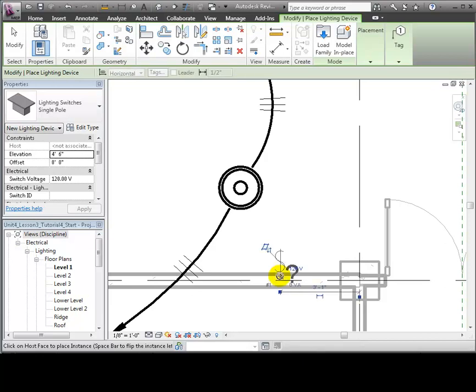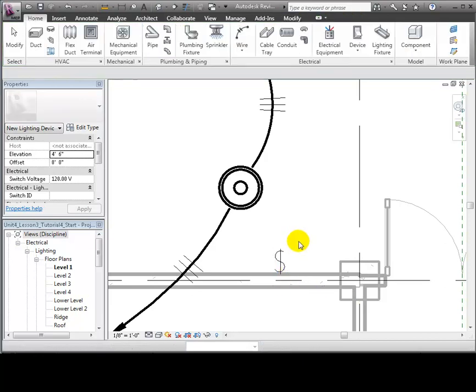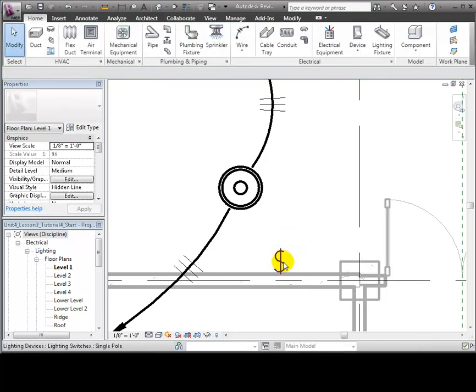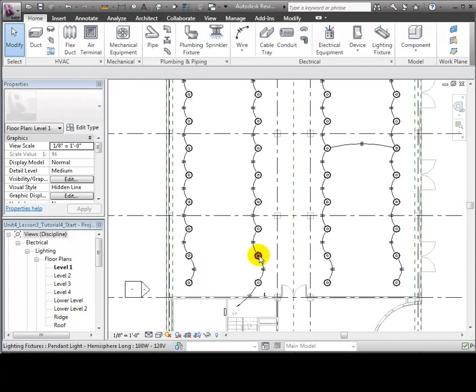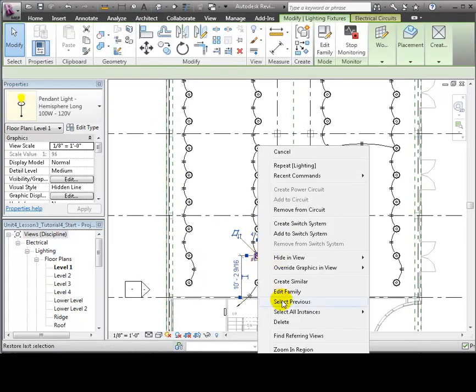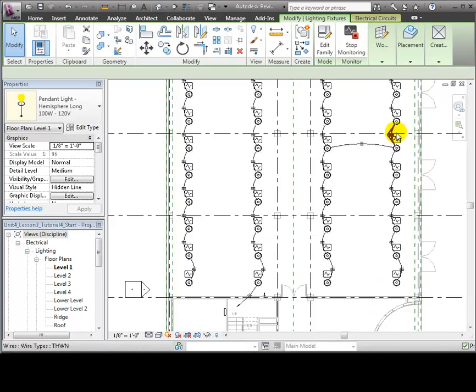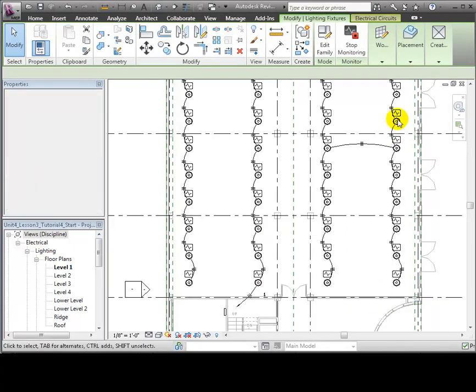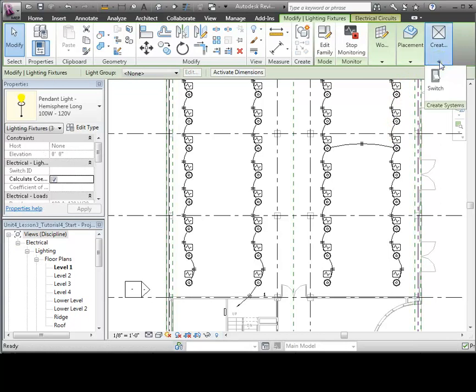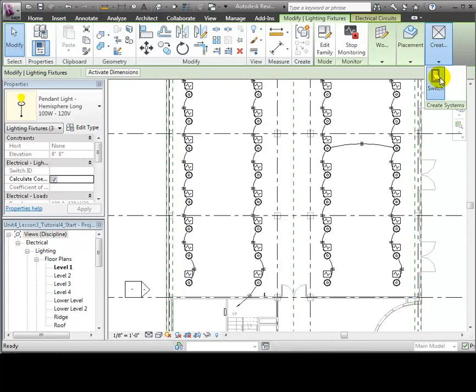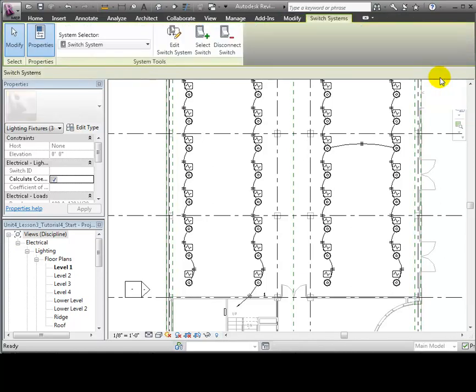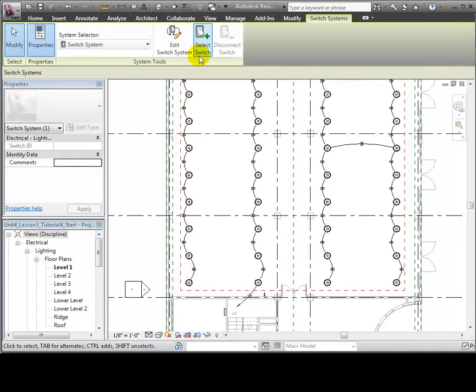Having placed the switch, we can now create a switch system to indicate which lighting fixtures this switch controls. Right-click on one of the fixtures, then use the Select All Instances Visible in the View command to select all the fixtures in the space. Open the Create Systems panel, and this time only Switch System tool is available, because a power system has already been created for these lights. Choose the Switch System tool, and the Switch Systems tab appears with options for creating the system.